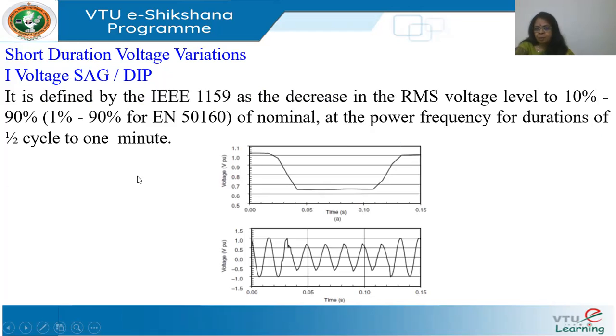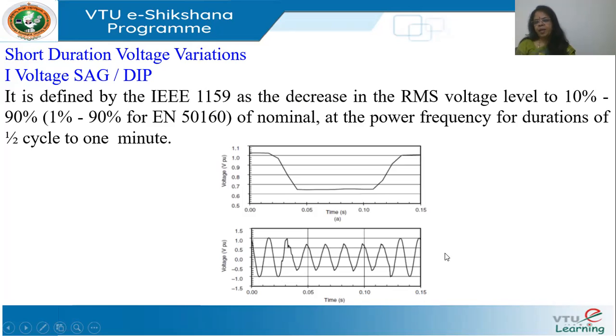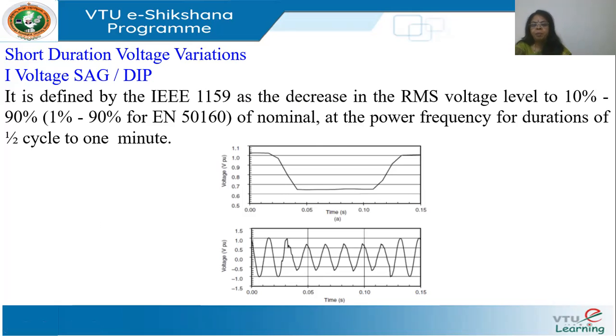A sag occurs at power frequency (50 Hz), lasting between half a cycle to one minute. The RMS value dips and then regains — the word sag indicates it comes down. The key difference from under voltage is the duration is less than one minute.